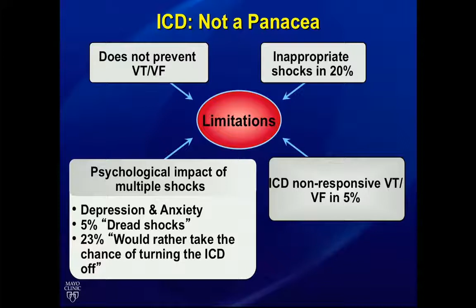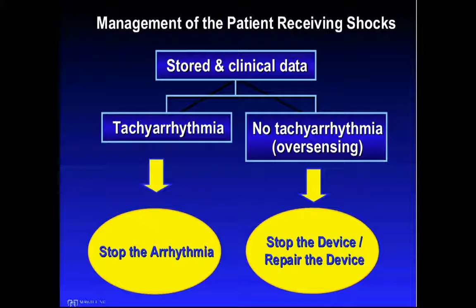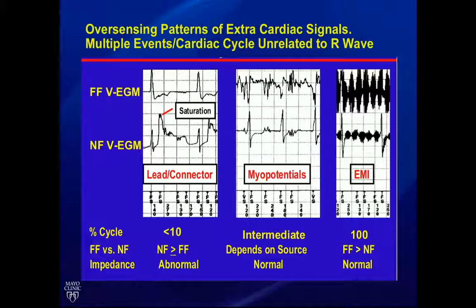And when you have a patient that you're called about in the emergency room having shocks, the main thought process and reason for interrogating the device is you have to figure out, what do I need to do? Do I have to stop the arrhythmia or do I need to stop the device? Is it appropriate or is it inappropriate? And the way interrogating the device works is you look for something like this. Non-physiological signals don't look like VT, don't look like ventricular fibrillation. External noise, electromagnetic interference, lead fractures with the wires rubbing against each other and producing electrical noise. In those situations, we stop the device, change the leads, figure out what the external noise is like.